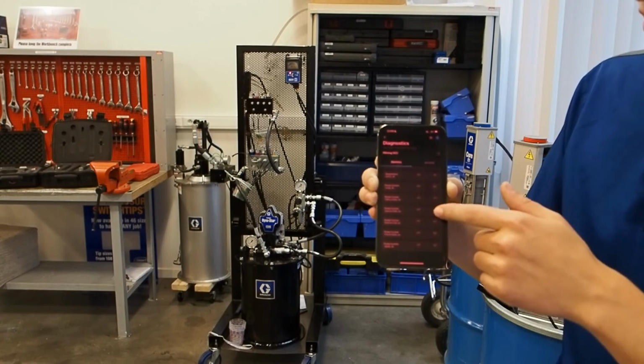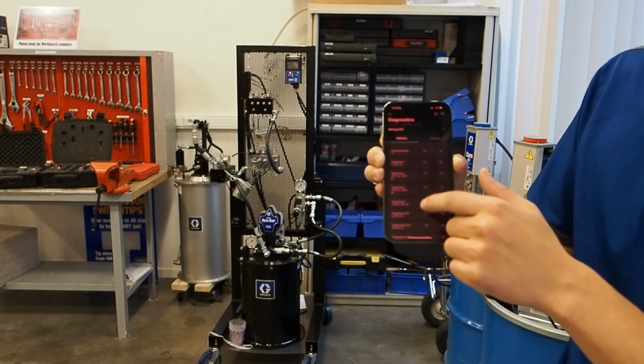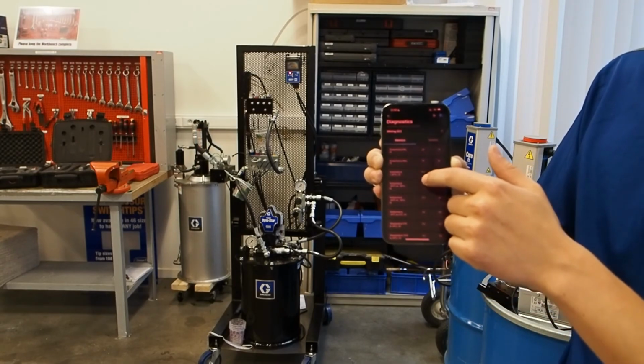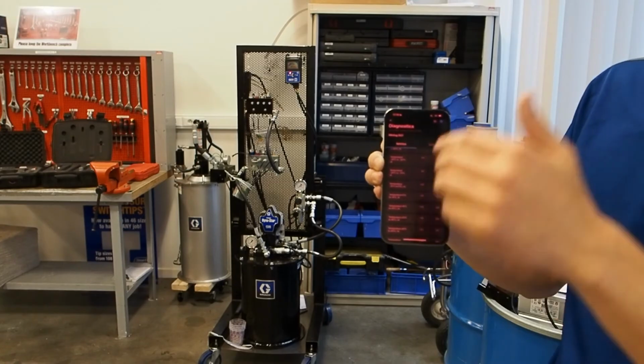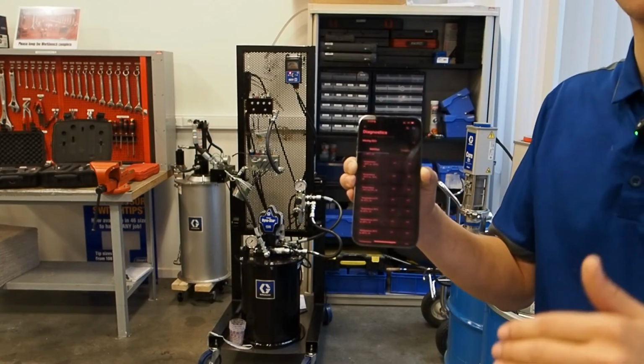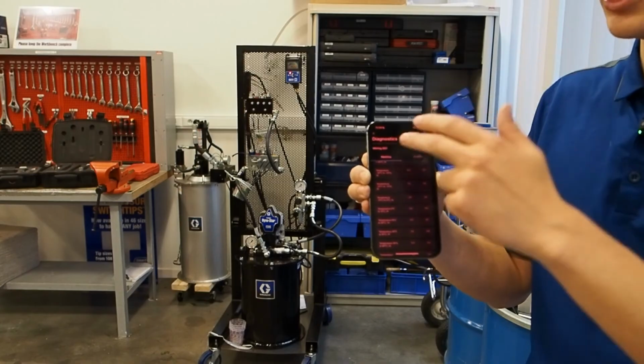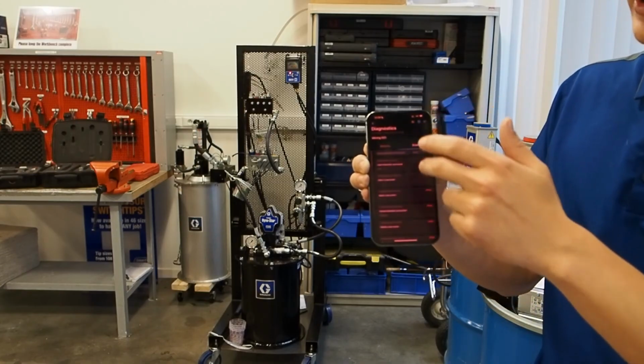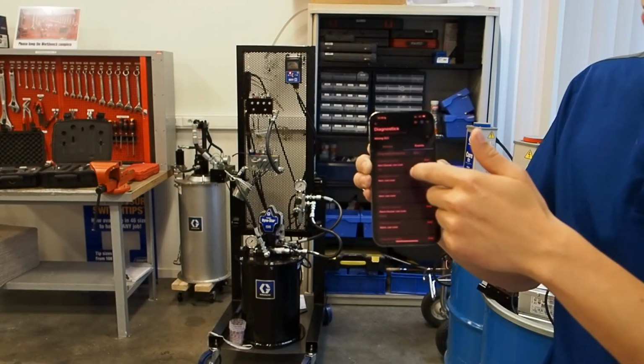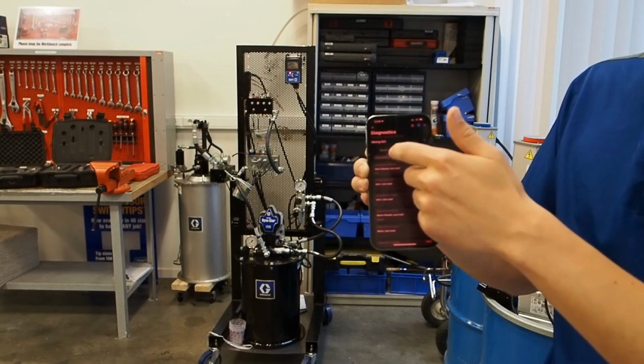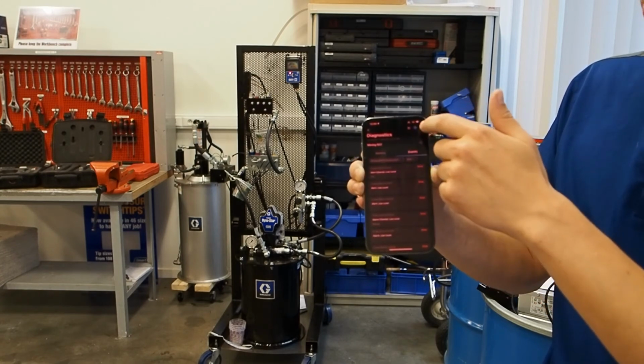I can also see different temperatures, like minimum and maximum temperatures. I can also see how much time it's been used below a certain temperature, or between 10 and 20 C. So it's a lot of data here. Also, I can see events here. Every problem that has happened, with date and time. There was an alarm for the low level, for example, or something else.